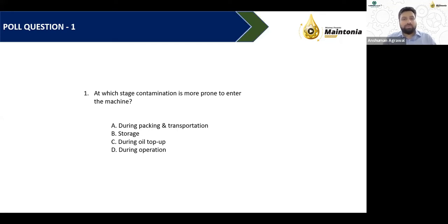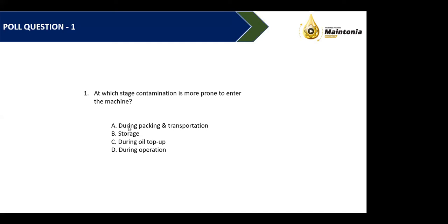And maybe Mr. Yogesh, with your experience of maintenance, can you give me some examples of how oil top up led to an immense amount of contamination getting added, especially if we talk about the control fluid oils, that's the FRF? Yeah, sure. When we talk about the top up of the oil, the methodology we adopt is the prime most reason for contamination ingress.